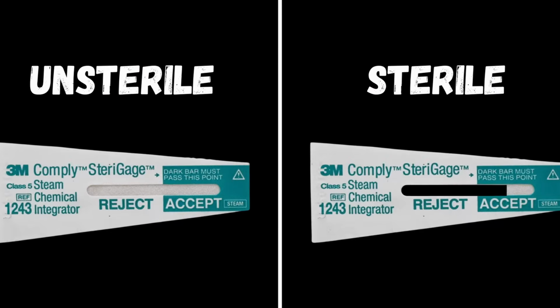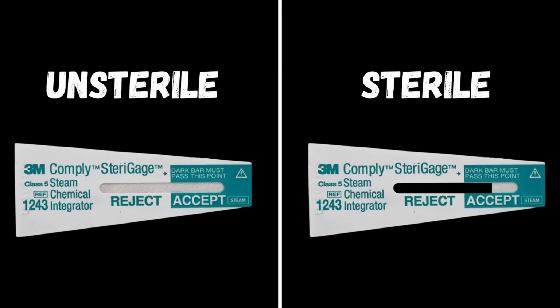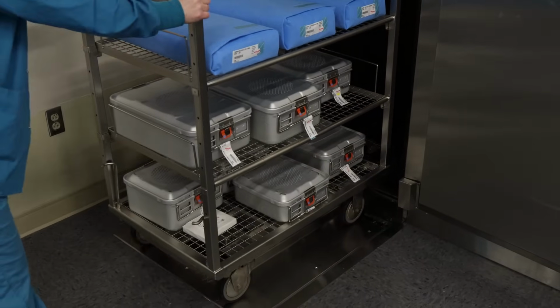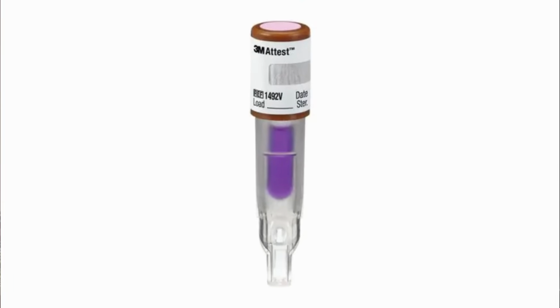Some integrators work kind of like a thermometer with the chemical in the strip. It takes a specific amount of heat to liquefy the chemical, and it takes a certain amount of time for that heat on the chemical to allow the staining up the strip to occur. Genius technology, really. And lastly, about verifying sterilization, we have taken it to the ultimate step, which is using biological challenge tests, mostly called bios. In a biological vial, there are millions of spore microorganisms that are highly resistant to heat and/or chemicals. And these are often put into the sterilization load with instruments to verify the killing power of the sterilizer. What better way to prove microorganisms are being killed than to actually do the process on really hard to kill live microorganisms?